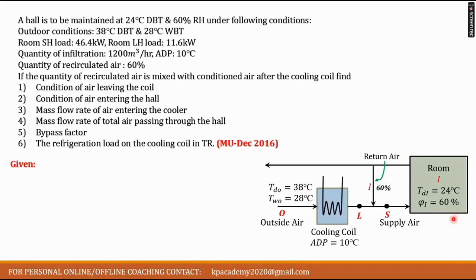Here we have another numerical on cooling load calculation from the Mumbai University December 2016 paper. This problem was repeated again in the same university paper, right? In the problem, we are given the condition that we have to maintain a hall or room at 24 degrees Celsius dry bulb temperature and 60% relative humidity. The outside condition is given as 38 degrees Celsius dry bulb temperature and 28 degrees Celsius wet bulb temperature.